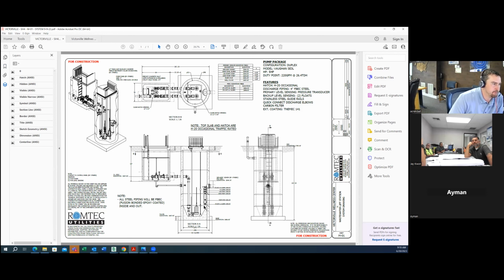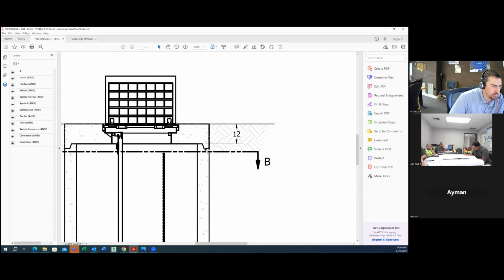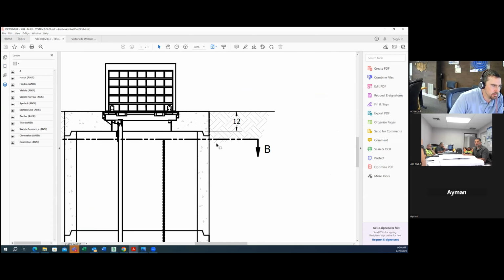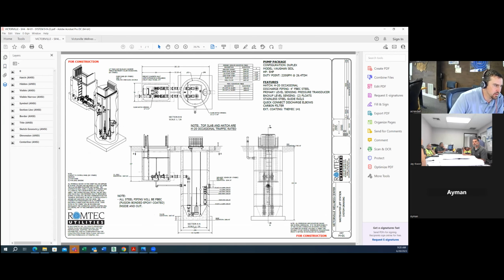Okay, and then the 2-inch conduits for the pumps would both go to the control panel, and you core your holes wherever it makes sense. The one thing we ask, if you're looking at this picture, is to try to get a couple inches below the joint of the top slab, so you're going through solid concrete and not trying to get through the joints and the sealants. There'll be sealants inside it, and if you just get right below it, we'll leave it up to you as to where you need to do it to get to the control panel by the path of least resistance.